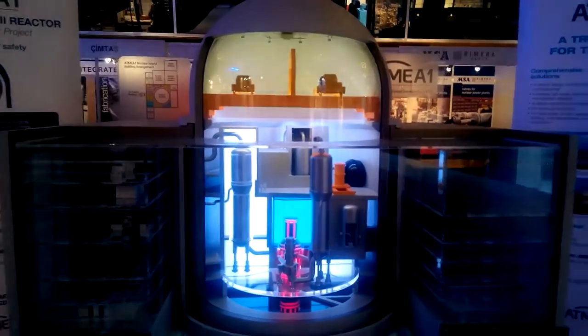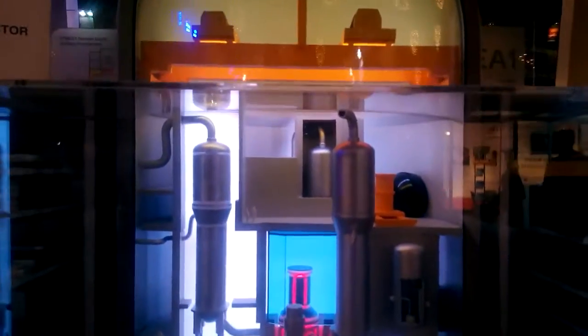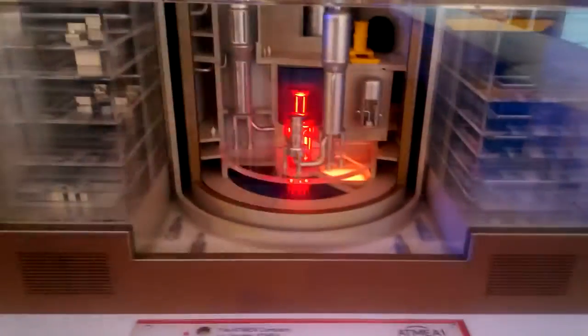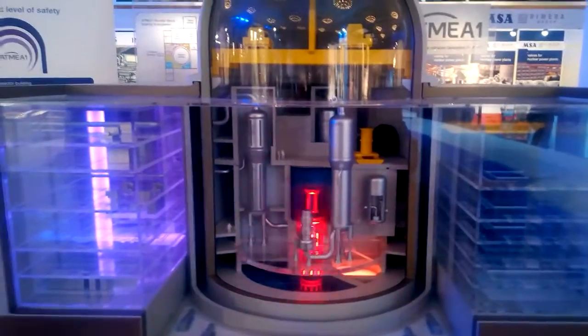The Atmea-1 reactor has been designed to assure safety and provide relief around the site area, even under extreme accident situations. For this, the reactor is fitted with a core catcher located beneath the pressure vessel, which will collect, maintain, and cool the core debris — or corium — over a long time, should the extremely low probability core melt happen. This core catcher will confine the molten core inside the reactor building, thus avoiding any damage to the environment. The diversified cooling chain of Train X, dedicated to severe accident management, will cool the molten core.